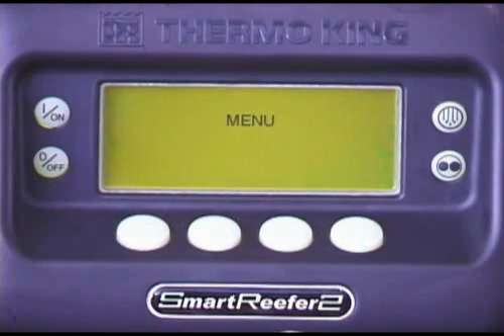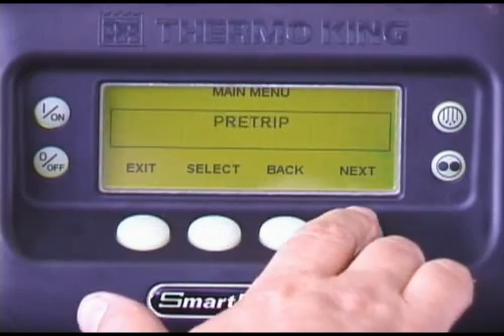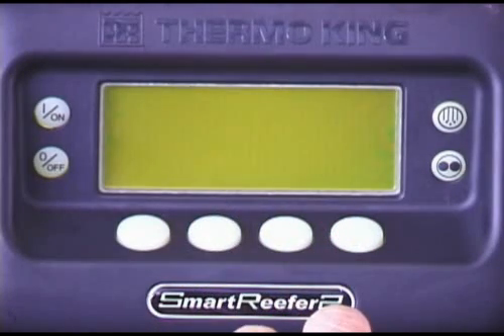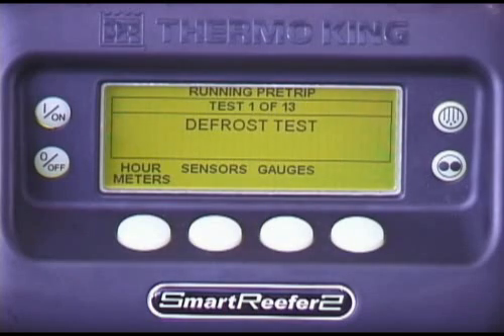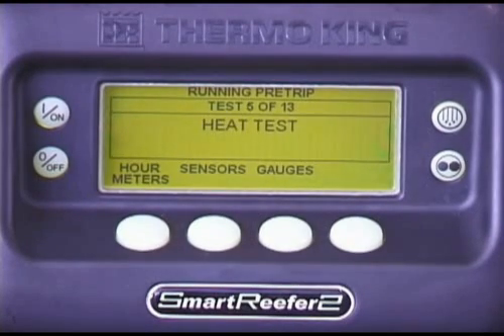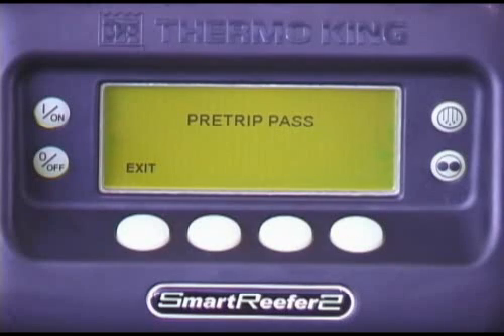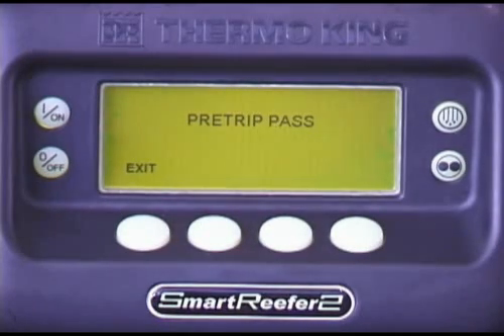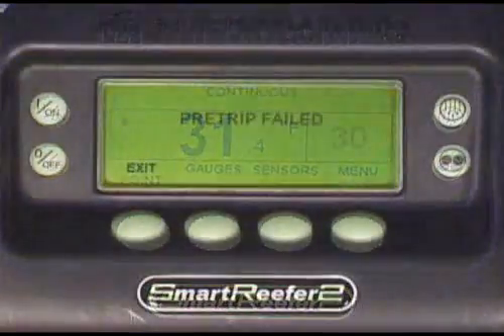Once any alarm conditions have been corrected and the alarms are cleared, press the Menu key. Press Next repeatedly until pre-trip appears. Press Select. Programming pre-trip mode indicates the pre-trip is being initiated. Once initiated, a series of tests will be performed to verify proper unit operation. When the pre-trip is complete, pre-trip pass should appear, indicating the unit passed the test. Press Exit to return to the standard display.